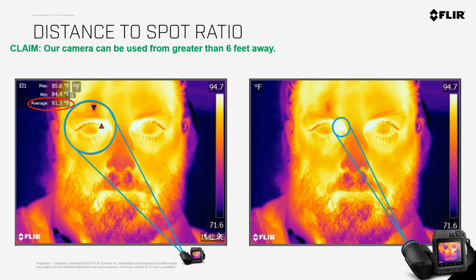So make sure that you have a camera with a strong distance to spot ratio, and that you're not more than 6 feet away, because the further away you get, the less accurate, or the less precise, your results will be. We can see here that inside of this circle, we have a max of 95.6 degrees, a min of 84.4, and an average of 91.3 degrees.